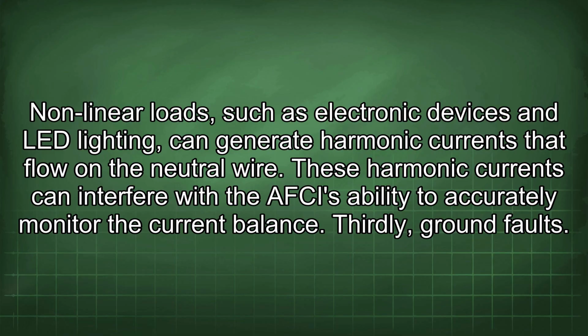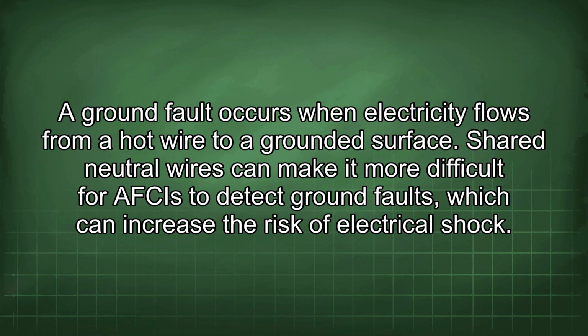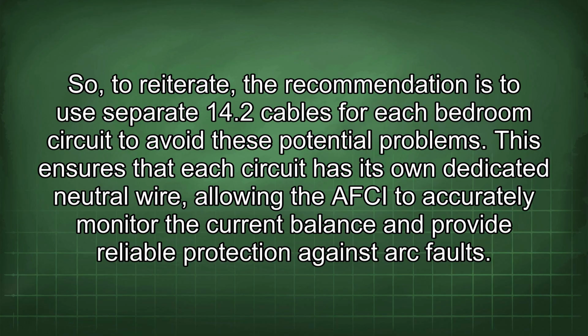Thirdly, ground faults. A ground fault occurs when electricity flows from a hot wire to a grounded surface. Shared neutral wires can make it more difficult for AFCIs to detect ground faults, which can increase the risk of electrical shock. So, to reiterate, the recommendation is to use separate 14/2 cables for each bedroom circuit to avoid these potential problems. This ensures that each circuit has its own dedicated neutral wire, allowing the AFCI to accurately monitor the current balance and provide reliable protection against arc faults.